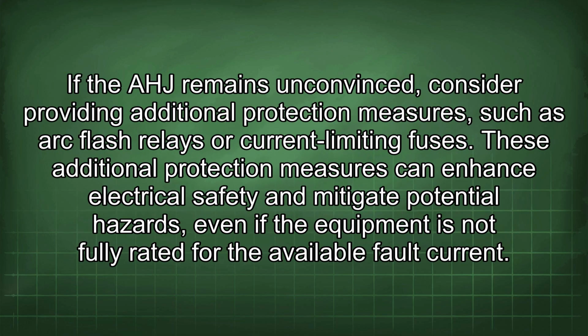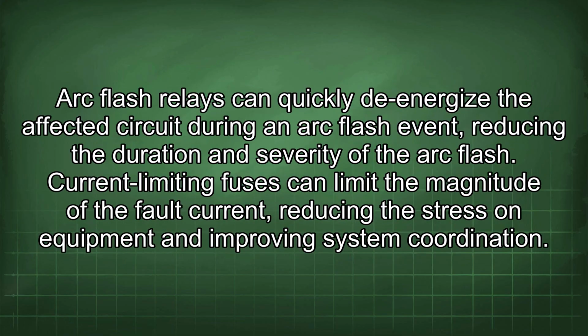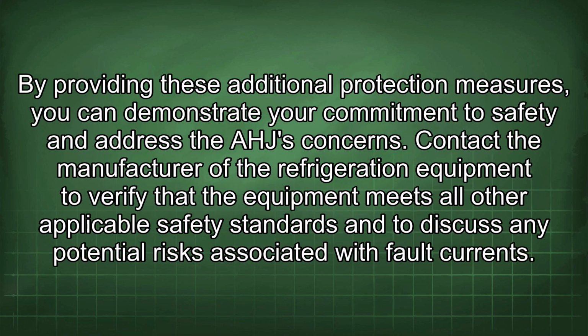If the AHJ remains unconvinced, consider providing additional protection measures such as arc flash relays or current limiting fuses. These additional protection measures can enhance electrical safety and mitigate potential hazards, even if the equipment is not fully rated for the available fault current. Arc flash relays can quickly de-energize the affected circuit during an arc flash event, reducing the duration and severity of the arc flash. Current limiting fuses can limit the magnitude of the fault current, reducing the stress on equipment and improving system coordination. By providing these additional protection measures, you can demonstrate your commitment to safety and address the AHJ's concerns.